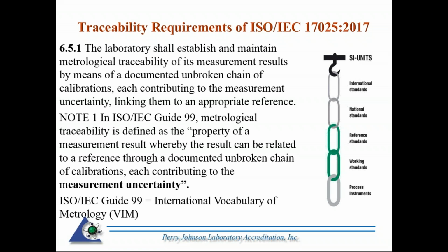So we have a simplistic view of a traceability chain on the right. If you're a lab and you send an instrument in for calibration and you need a traceable calibration, say you have a test weight and you send it to an accredited lab, you're going to get a report back from that lab with a measurement uncertainty on it. So the traceability chain includes measurement uncertainty, where each time you add a link, you add to the measurement uncertainty. Why?